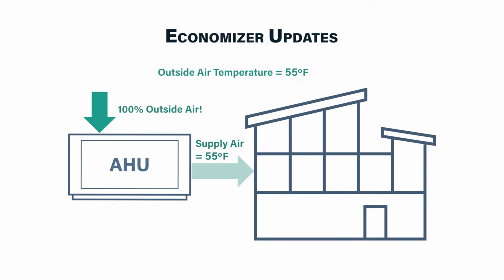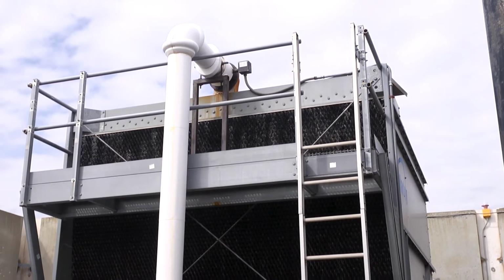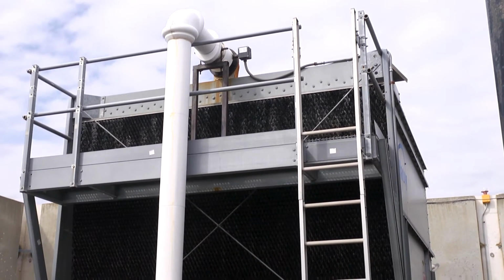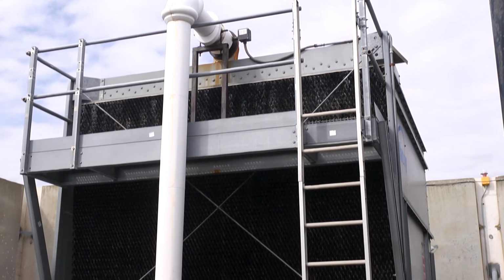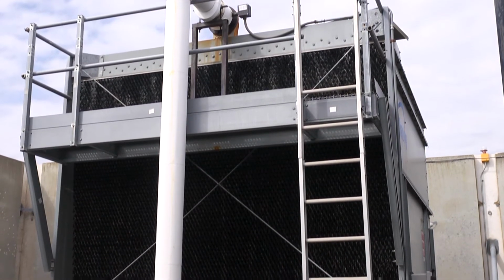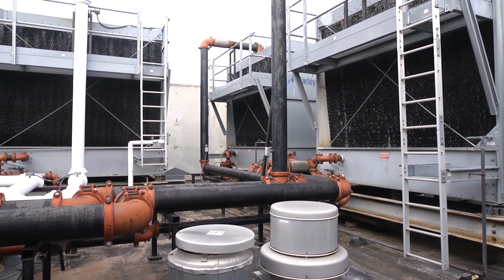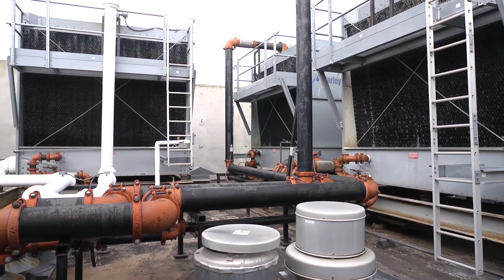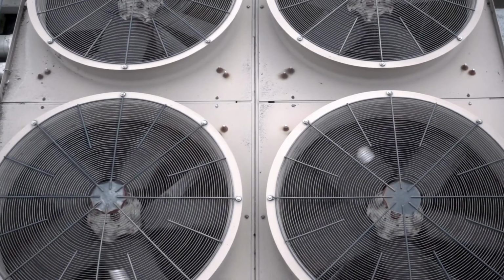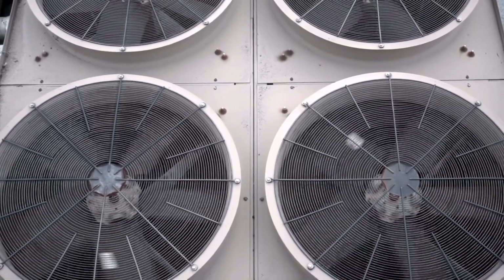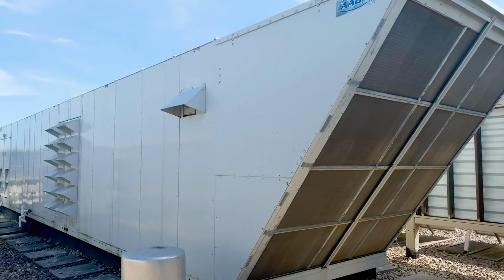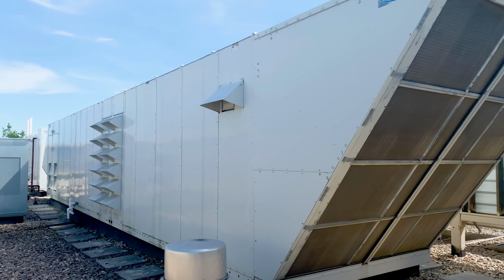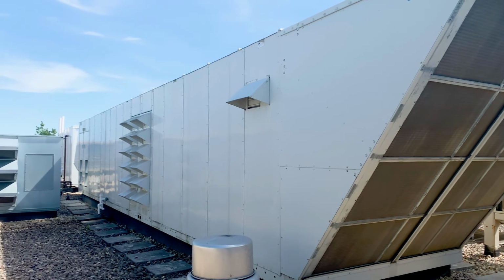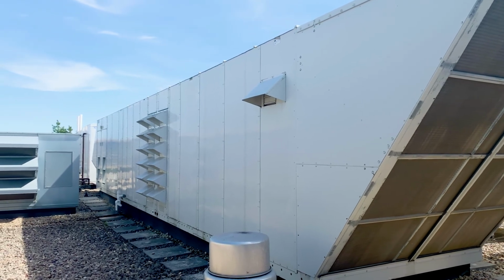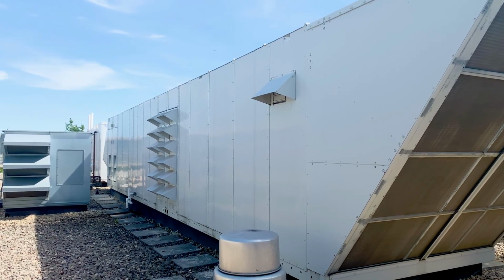A water-side economizer is similar to an air-side economizer, but instead of using outside air to cool a building directly, we'll use outside air over a dry cooler to cool our chilled water. This will keep us from having to run our chiller compressors when it's really cold out. Many of the code updates apply to both types of economizers, but I'll be focusing on air-side economizers as those are more commonly used than water-side economizers.